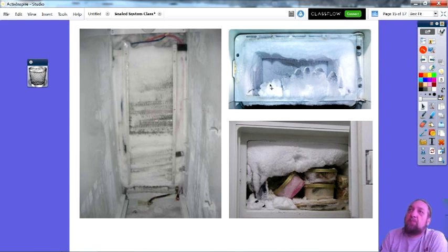What do you think about the top right picture? Do you think that's a defrost or another type of problem? Another defrost problem? Yeah, and in all these pictures, this one here also is a defrost problem. Both these two on the right are what they call manual defrost units. The evaporator is called a shell evaporator, and it wraps all the way around the food and does not have a defrost heater, so you have to manually defrost it.